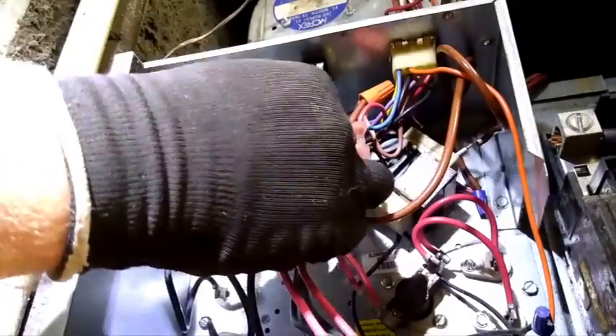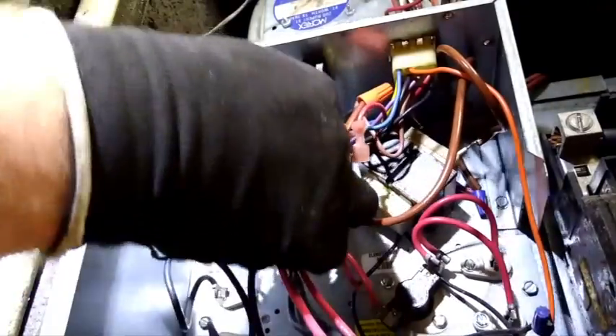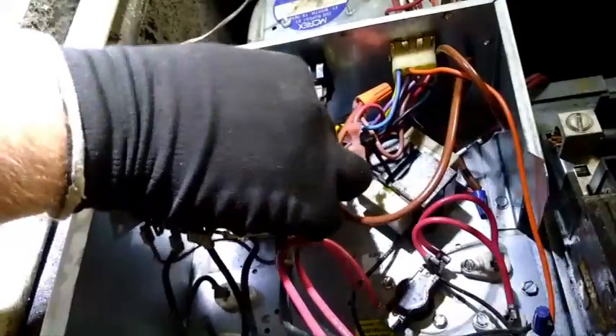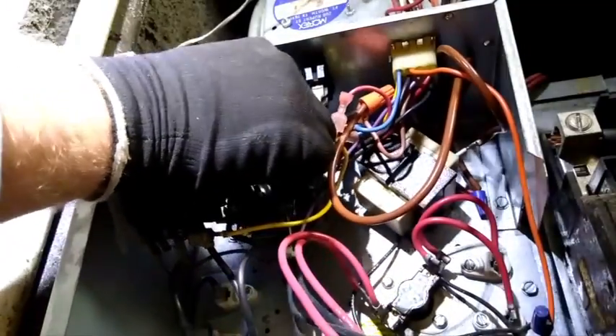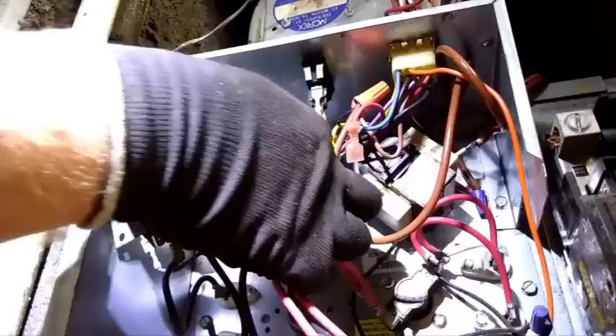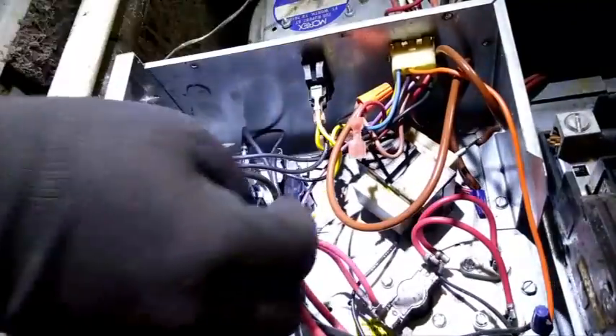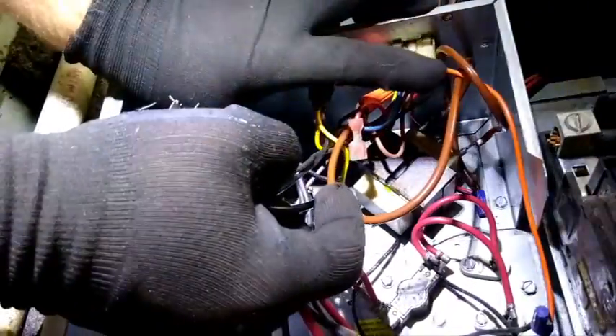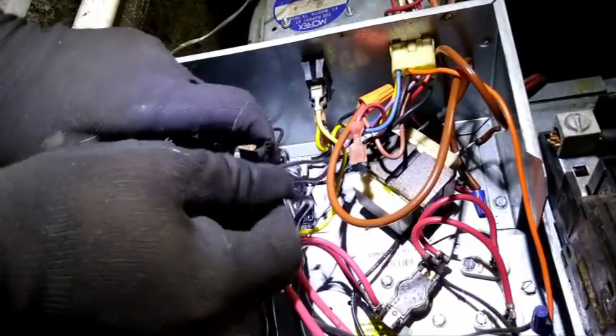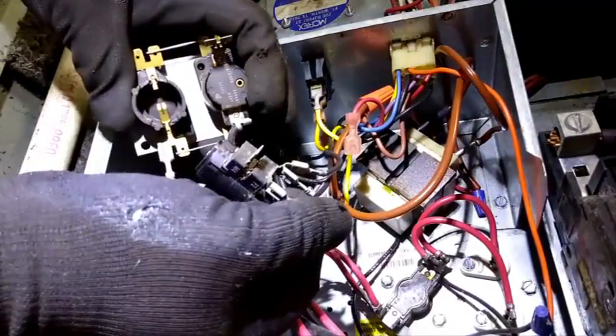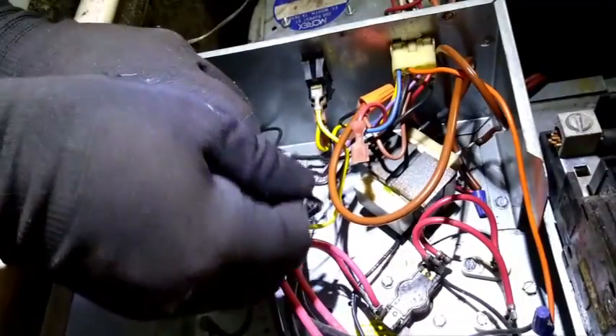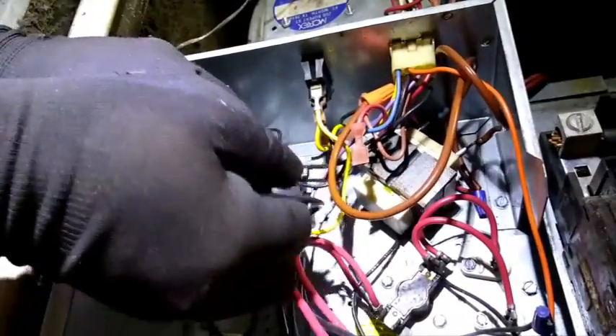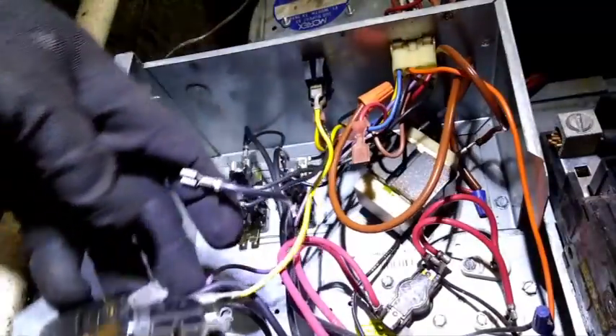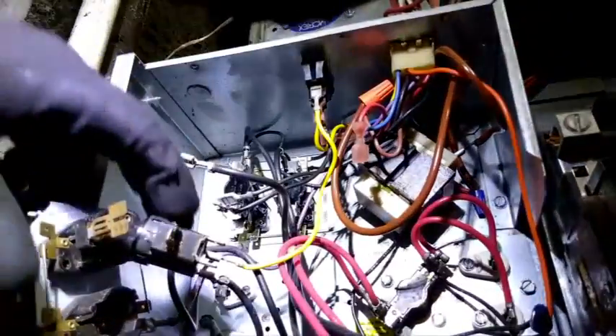You have the one yellow wire, that's the wire coming off of the sequencer going to the blower, because on an electric furnace, your sequencer operates the blower, meaning it'll send a voltage signal to the blower relay. You'll have a one pole normally open, one pole normally closed blower relay, and on the normally closed side, you'll have voltage passing through in heat mode. When you don't have that G call, when you just have a W call, the sequencer clicks on, sends that voltage up to the relay, and passes straight through, and usually operates the blower at a lower medium speed. The cooling's typically high speed.